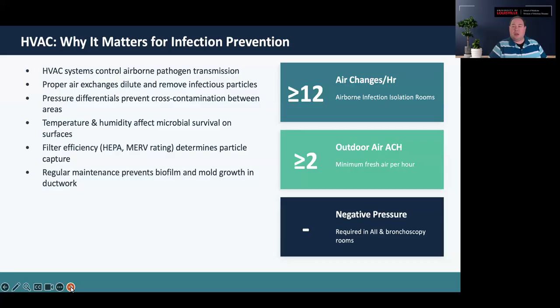Generally, for airborne isolation rooms we want greater than 12 air exchanges per hour, with at least two fresh air exchanges coming in from outside. In California, that's a different conversation—wildfires can complicate fresh air exchange. But remember, on the exam they'll only ask general questions, not anything specific to Georgia or California—just what the standards say: 12 or more air exchanges for airborne isolation, and greater than two fresh air exchanges.